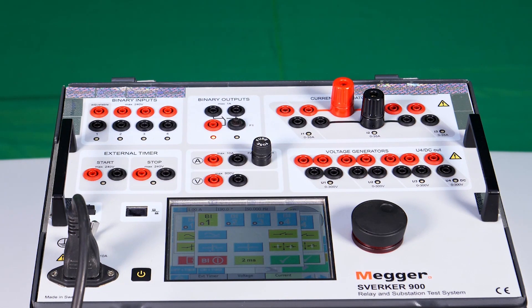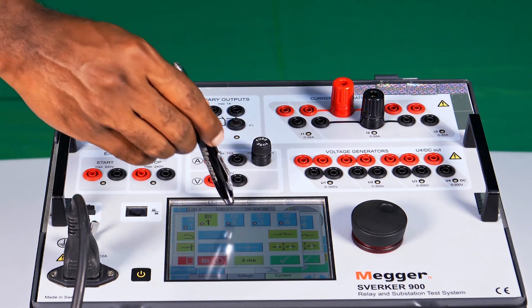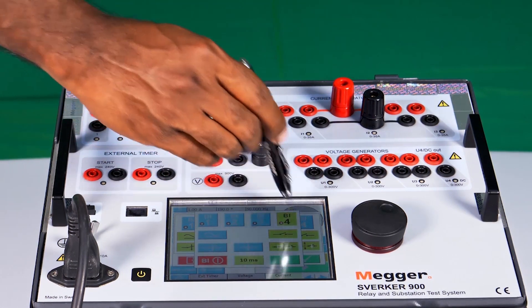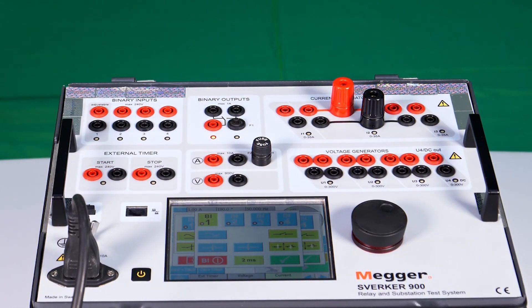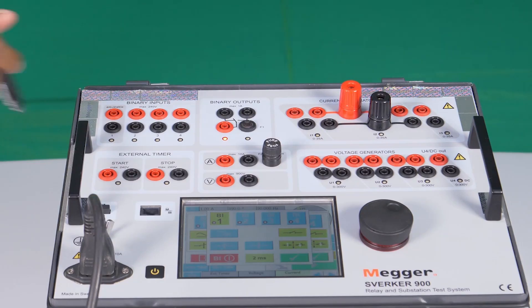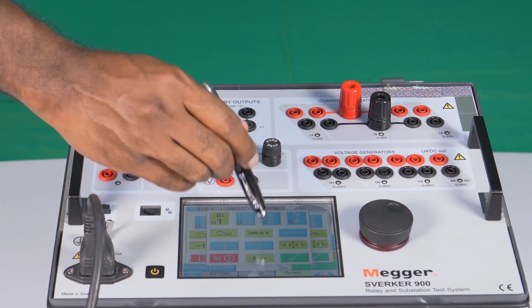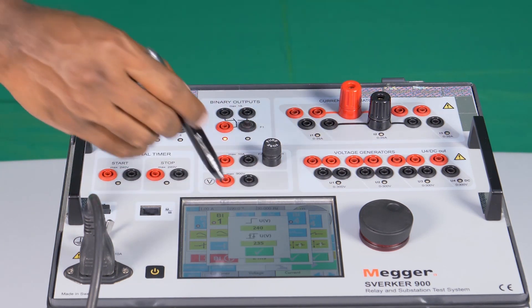The first binary input, number 2, number 3 and number 4. The first binary input alone can be configured for an adjustable voltage threshold which can be set between 5 volt to 240 volt.